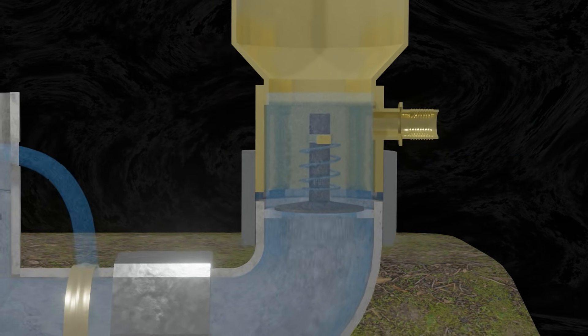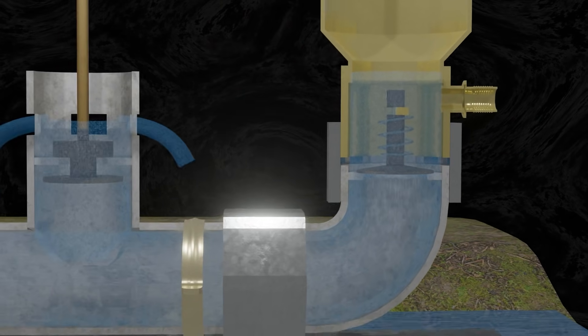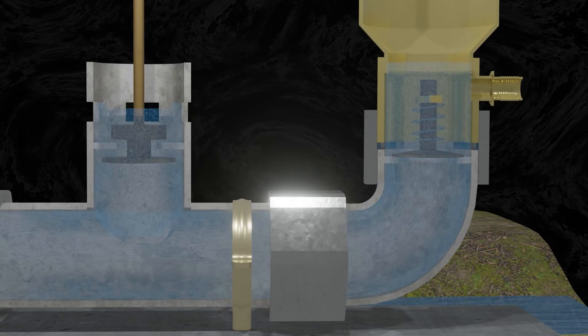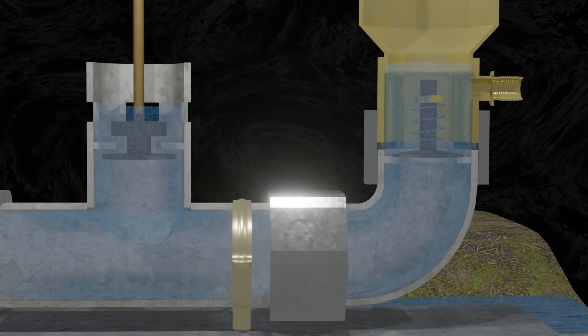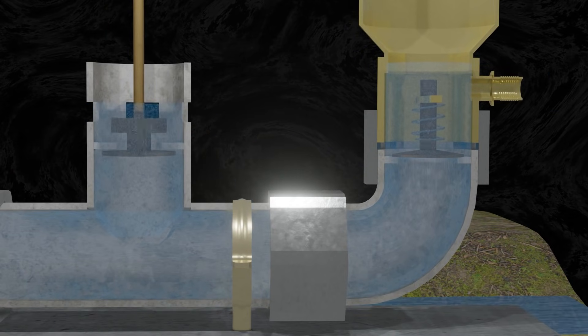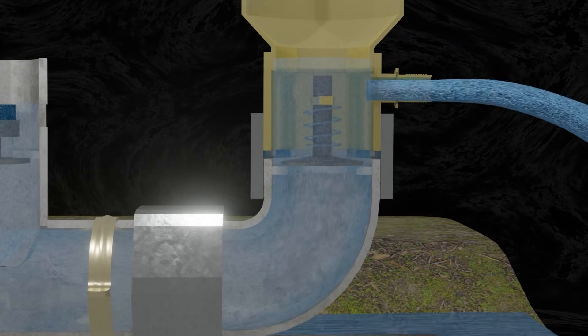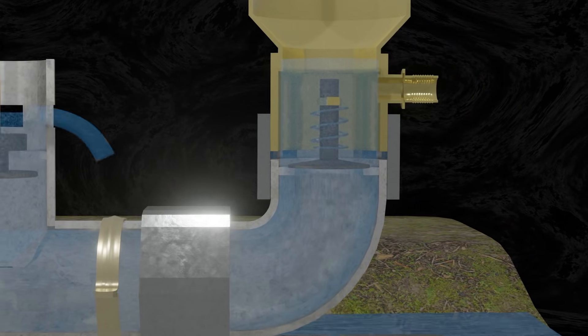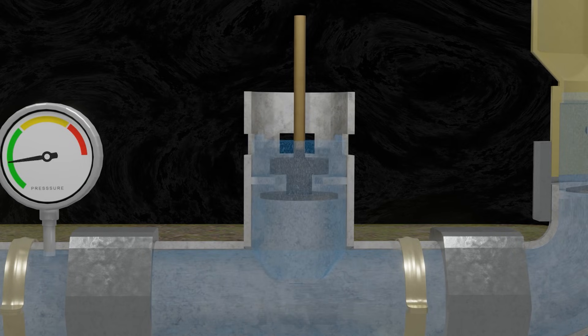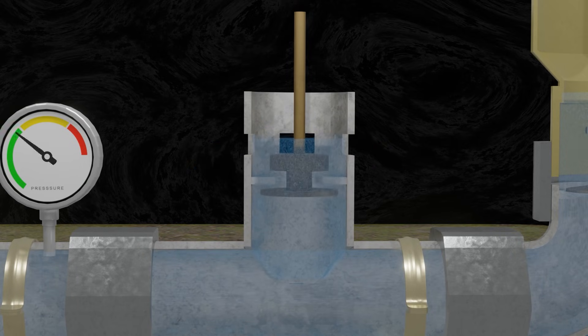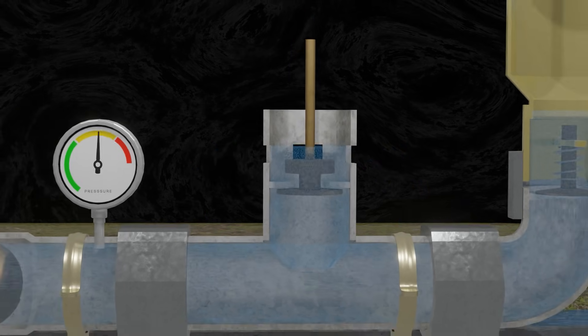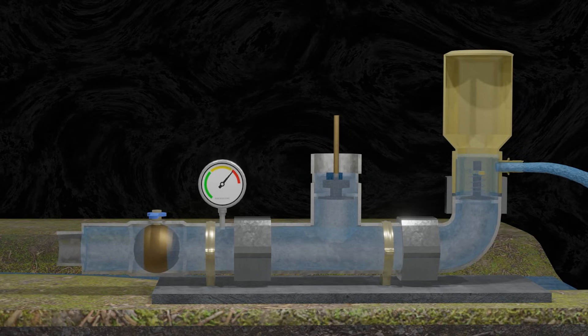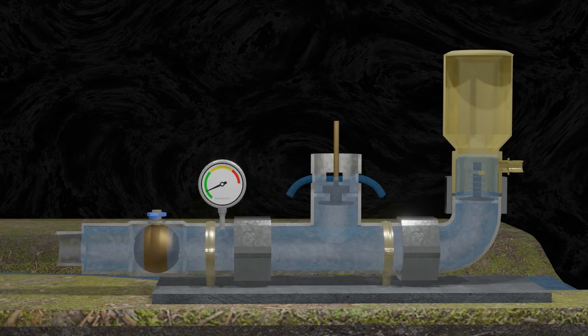When the effect of water hammer is done, the pressure inside Hydram will return to initial pressure. It will normalize the position of both valves. Conducting valve will close by spring force and hydrostatic force from water on top of it, while waste valve will move down because of gravity. When both valves are in their original position, Hydram is ready for the next cycle.